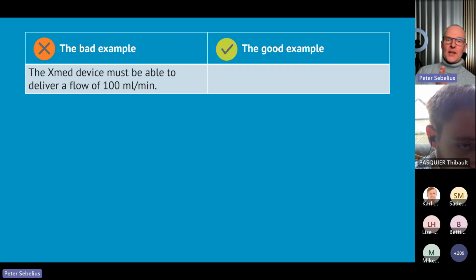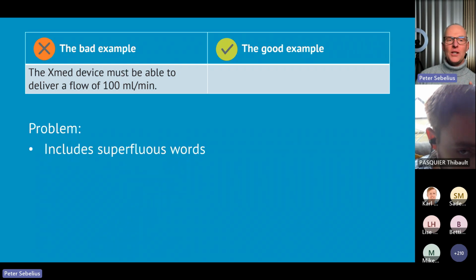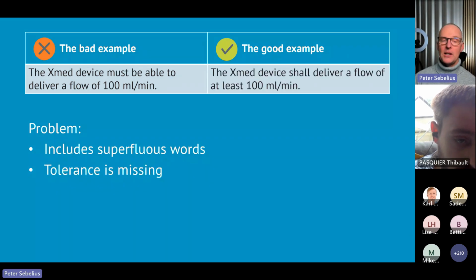Now, let's see if you can spot the problem with this requirement, and that is that the XMED device must be able to deliver a flow of 100 milliliters per minute. Now, if we follow the principle that we brought up with the previous requirement, we should remove the be able to, because those words are superfluous, but there is actually one more issue with this requirement. And the problem is that 100 milliliters per minute is not specific enough. And by that, I don't mean that it should say 100,000 milliliters per minute. I mean that the R&D engineers would not know if it should be at least 100 milliliters or not more than, or 100 milliliters plus minus 2. The requirement is simply missing tolerances. So this must be specified in greater detail. And for example, it should maybe say the XMED device shall deliver a flow of at least 100 milliliters per minute. That would be the way to go.